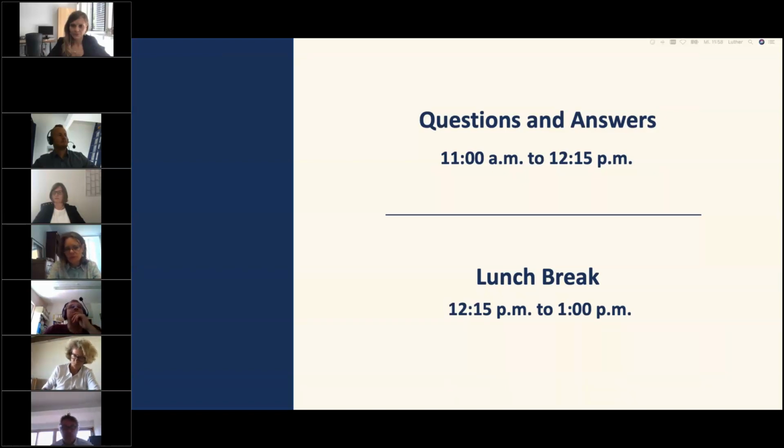So at this time, I can only state, please look at the wording very closely in the regulation, and do as the regulation says. And if you classify, give the reasons how and why you classified in this way, depending on the intended purpose. It's like a prayer in church. It's intended purpose and intended purpose and intended purpose. And this is how you classify, and this is how you define your justification in your technical documentation for the risk classification. This needs to be provided to the notified body. This is also the same today, and the notified body has the opportunity to agree or to disagree. In case of disagreement, you would have to seek guidance from the competent authority.